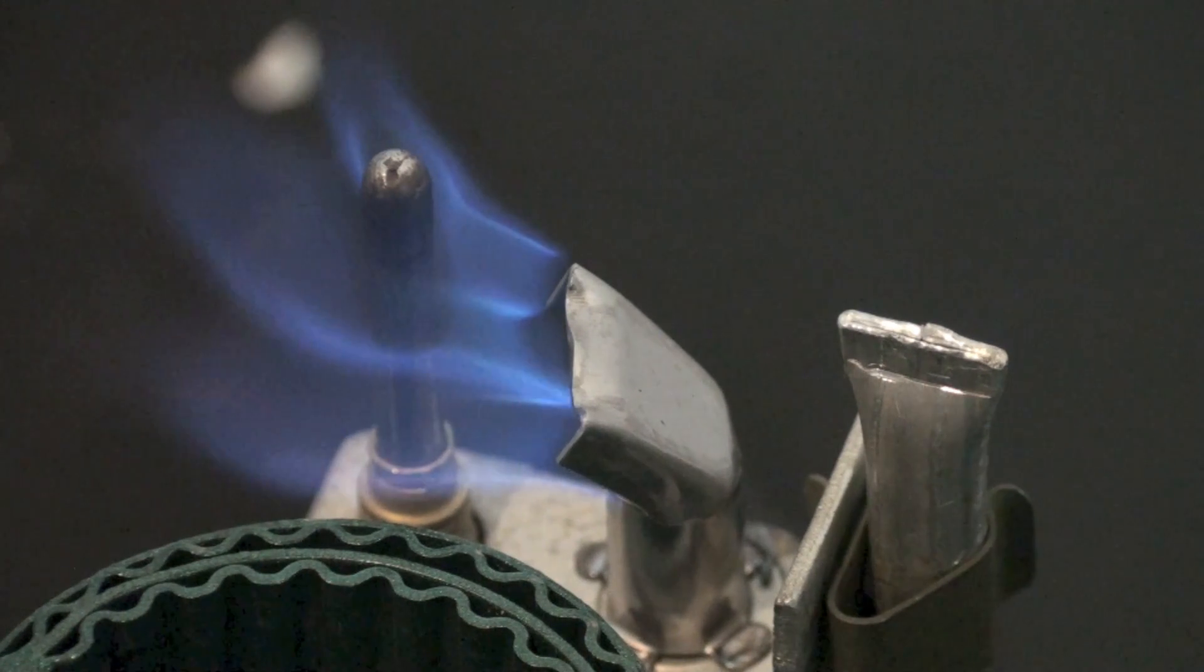It's touching the thermocouple. It should touch the thermocouple three-eighths to half an inch. It should be higher into the flame or lower into the flame. And that looks about right.